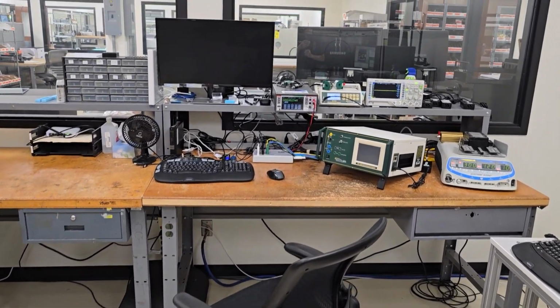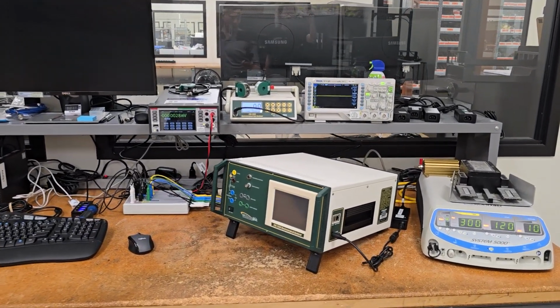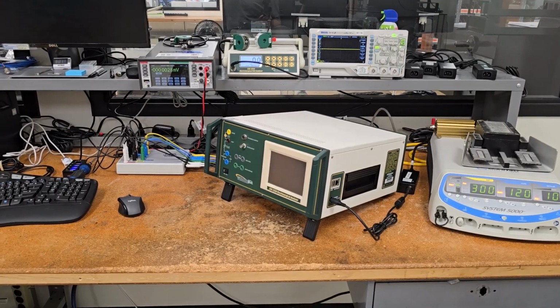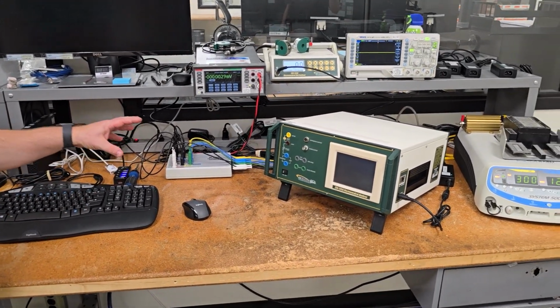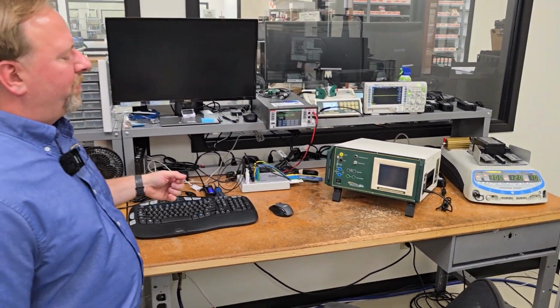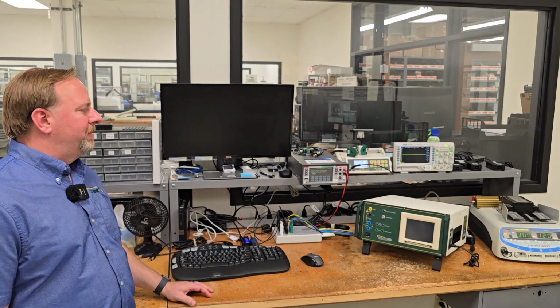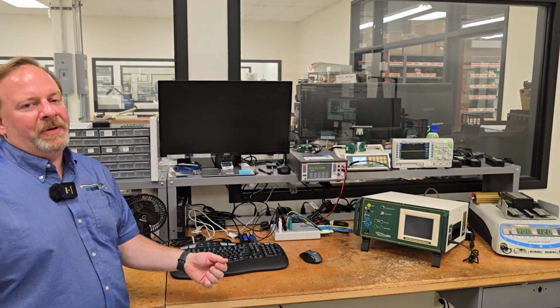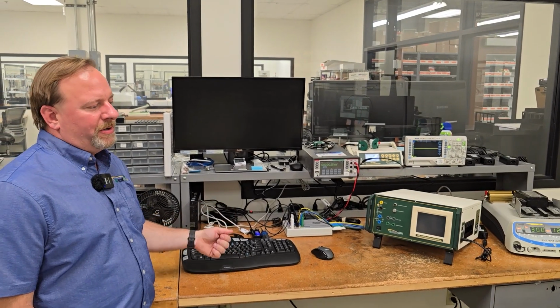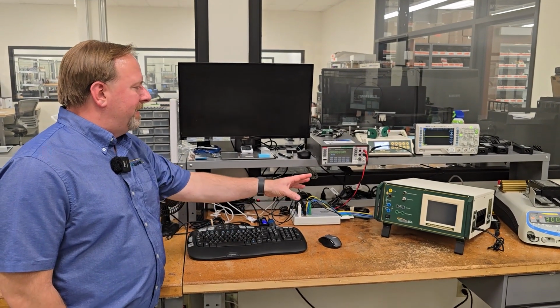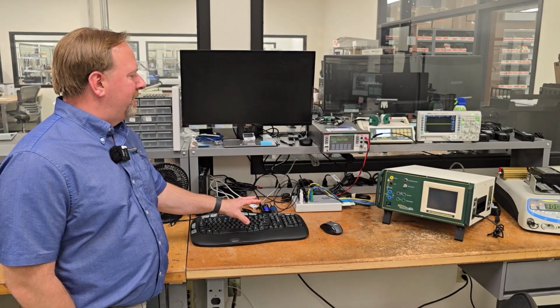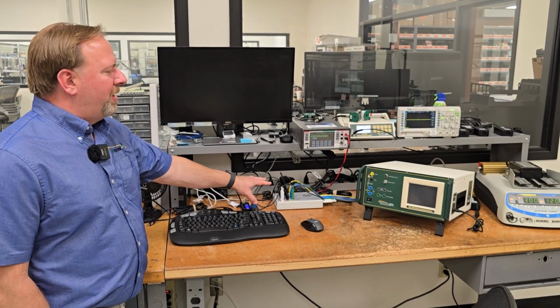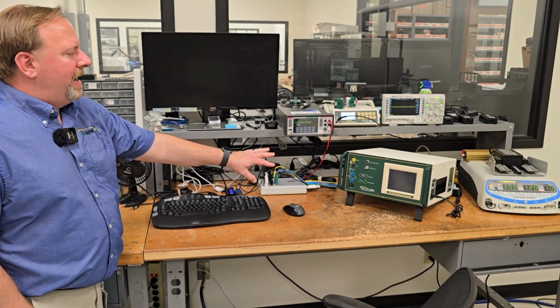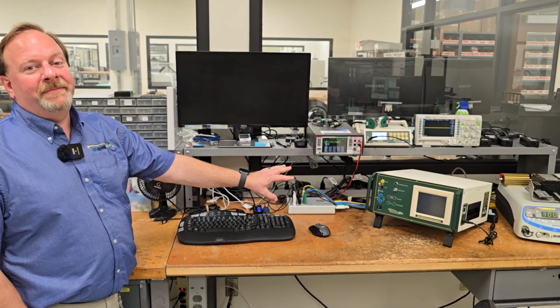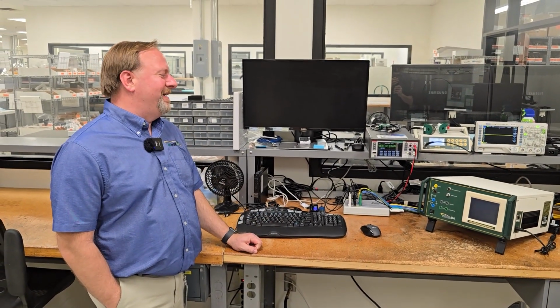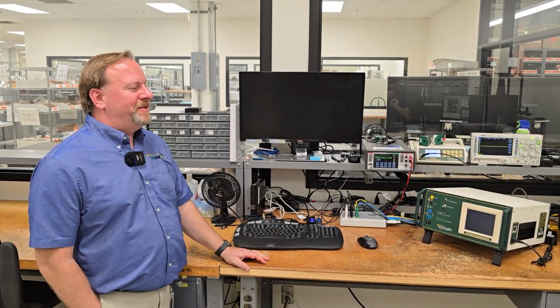Right. Again, this is routine calibrations for ESUs. So again, by bringing in automation, we can bring that repeatability and that consistency to the testing procedure. The tech doesn't need to remember the procedure. They don't need to open a book or find a service manual. They plug the device into the automated bench. The computer runs the test. In this case, we're measuring all the resistances of the ESUs. And if anybody has done that manually, there's a lot. So there's a lot of measurements to take, and this automates that and makes it much easier and consistent.